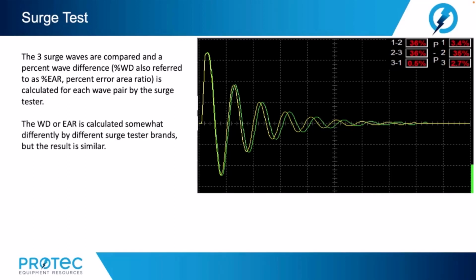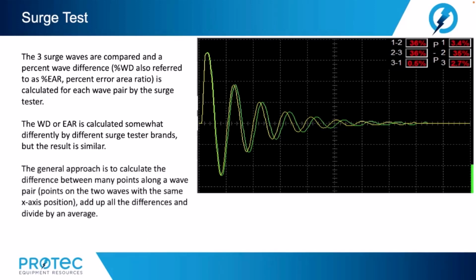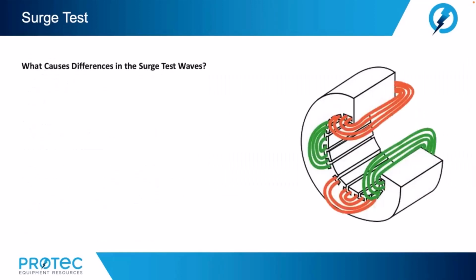The WD or EAR is calculated somewhat differently by different surge tester brands, but the results are similar. The general approach is to calculate the difference between many points along a wave pair, points on 2 waves with the same x-axis position, add up all the differences and divide by an average. If the percent WD is too high, the surge test failed. So what causes differences in the surge test waves?